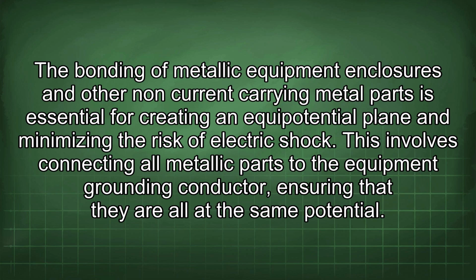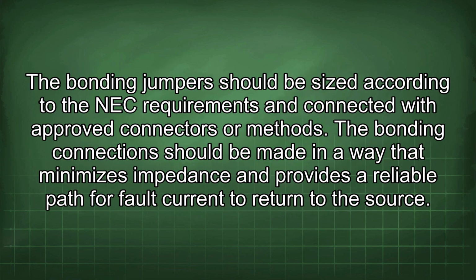This involves connecting all metallic parts to the equipment grounding conductor, ensuring that they are all at the same potential. The bonding jumper should be sized according to the NEC requirements and connected with approved connectors or methods. The bonding connection should be made in a way that minimizes impedance and provides a reliable path for fault current to return to the source.